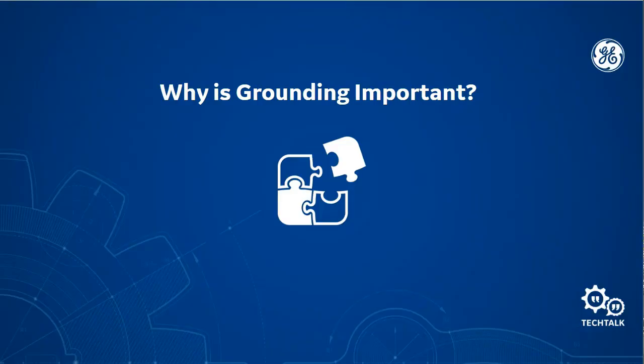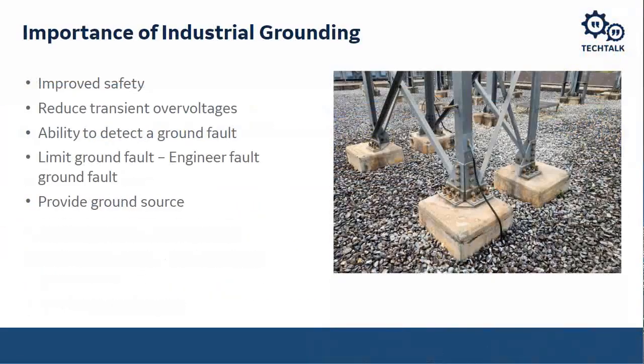So the why. Why is industrial grounding important? Why is grounding important, especially in industrial facilities? And why do we need to talk about it? Grounding provides improved safety by allowing detection of faulted equipment. It also stops transient overvoltages, especially notorious in ungrounded systems. In ungrounded systems, when you have a phase-to-ground fault, the faulted phase becomes your neutral or your reference. And the unfaulted phases then get elevated to a phase-to-phase voltage. So you're going to stress your insulators on an ungrounded system for a phase-to-ground fault to the phase-to-phase voltage levels.